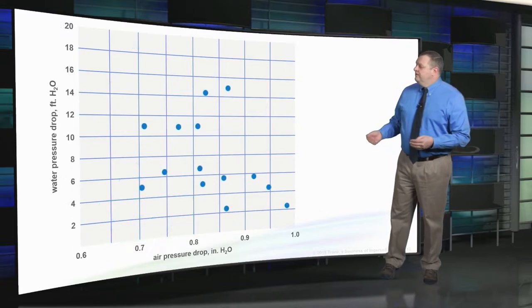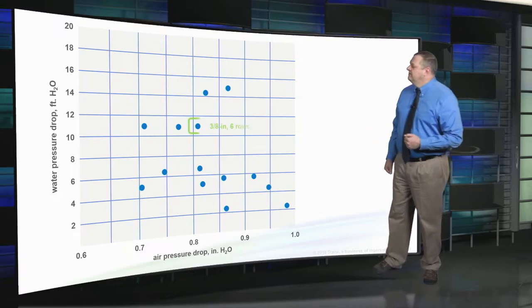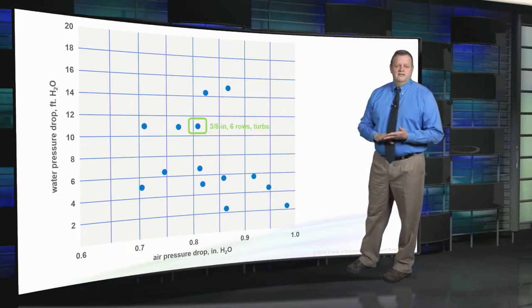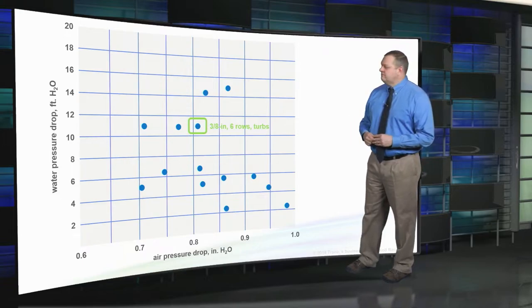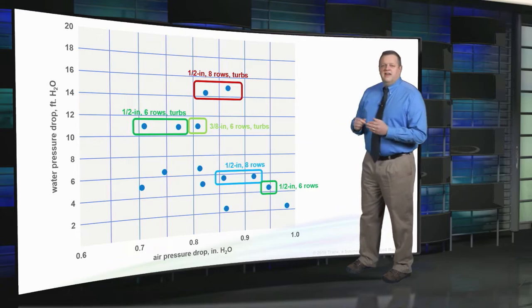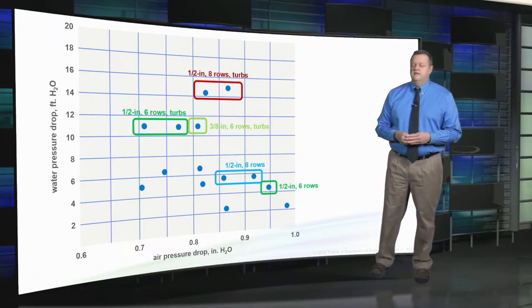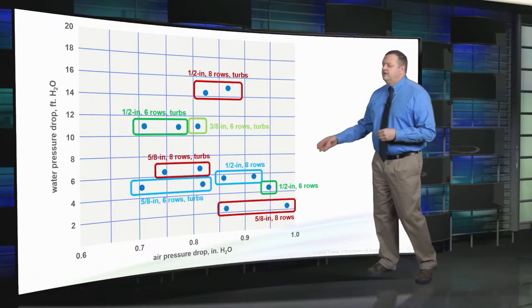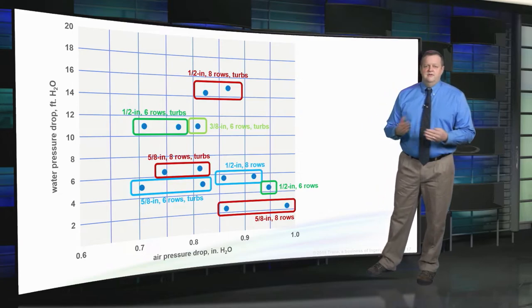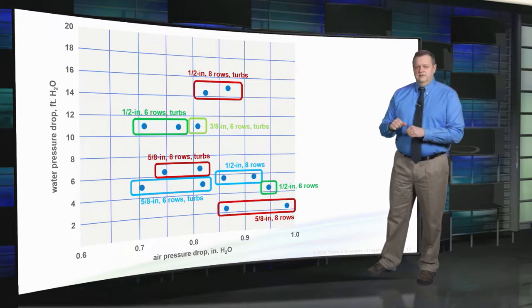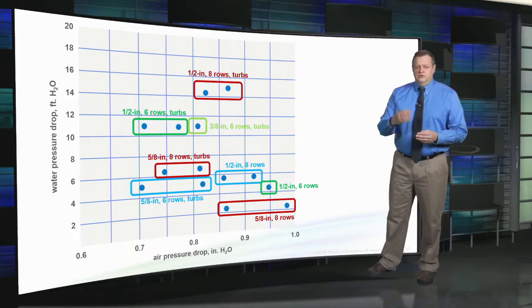This leaves 14 options. One coil uses 3/8 inch tubes, making it the least expensive choice. A group of coils uses 1/2 inch tubes — some with 6 rows, some with 8, with or without turbulators. The last group uses 5/8 inch tubes, again 6 or 8 rows, with or without turbulators. Turbulators are devices inside the tubes that increase fluid turbulence, which improves heat transfer.